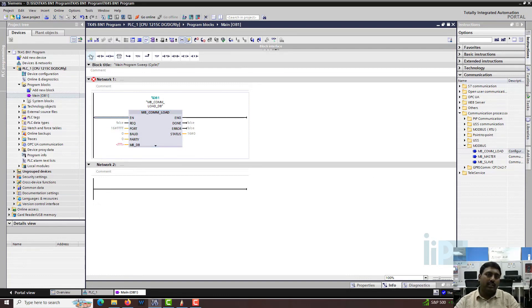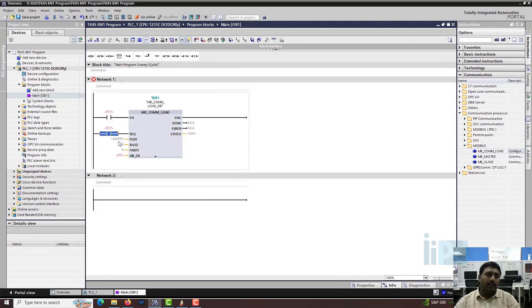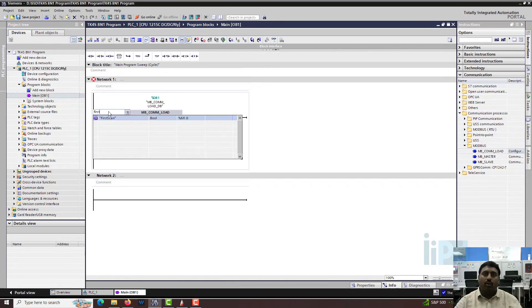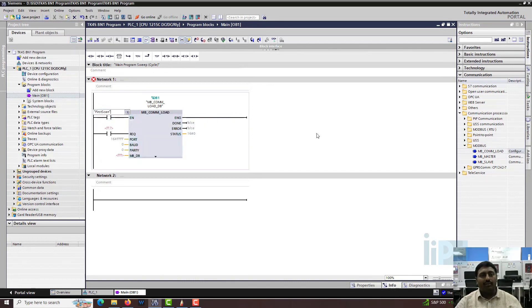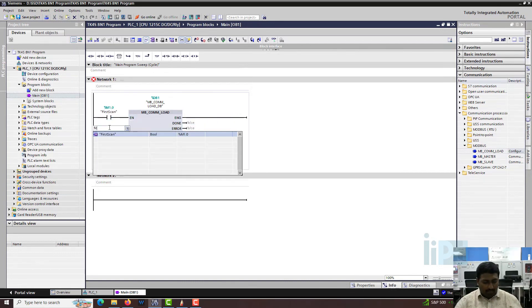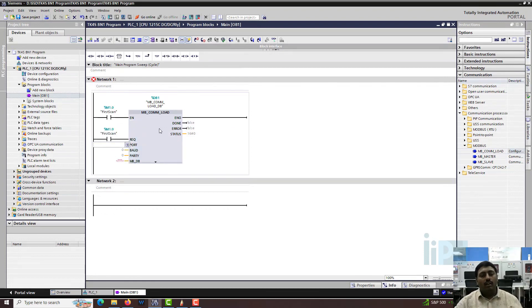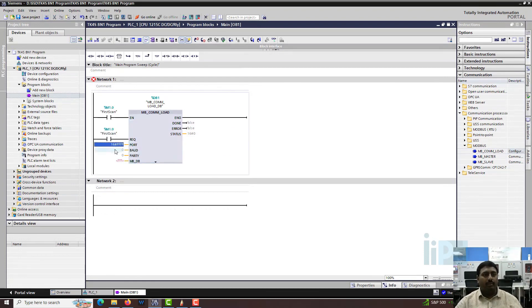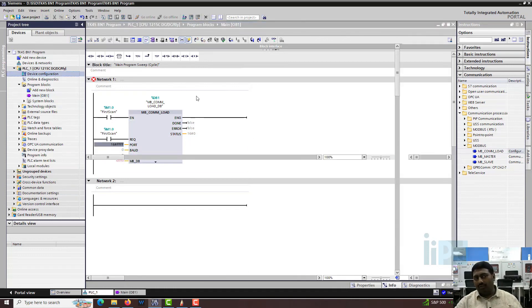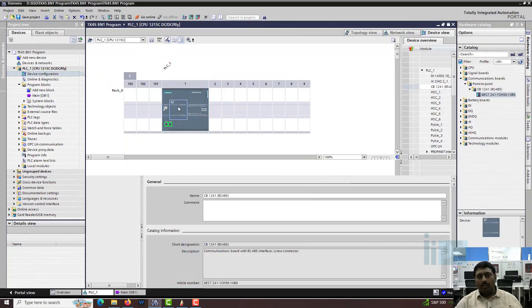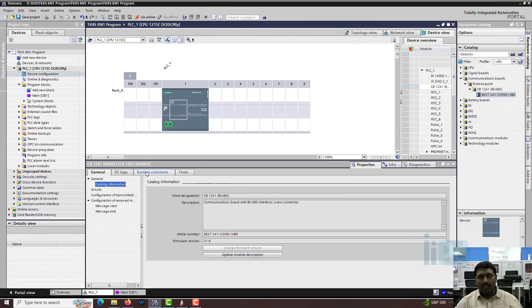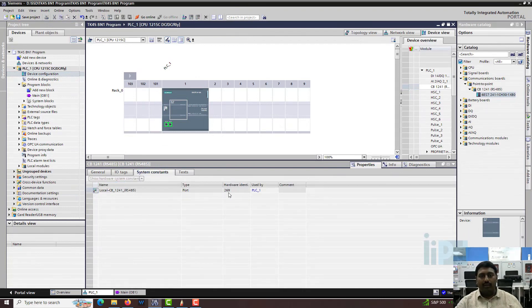For the enable input, let's use the first scan signal - this is what we enabled in the system and clock memory. Now it is asking for a port number. To find it, go to your device configuration, go to your Modbus device, and check the system constants - the port number of the device is 269.